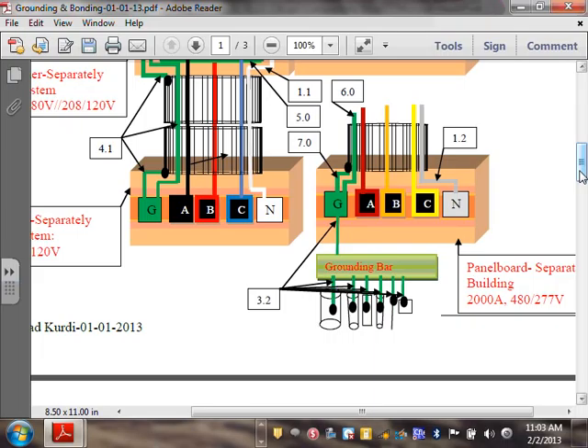I have 5 conductors. You have to pull the 3 phases, the neutral, right? Your neutral has to be sized, and you also have to pull an equipment ground conductor. Now the equipment ground conductor is the same way, except you're going to size it now for 2,000 amp. That's why I call it number 6. No changes. It's just another subpanel. Number 7, guys, is also the equipment bonding jumper, load side, same size. Same size, meaning the same process, except it's going to be sized for 2,000 amp. And what's the size, guys, that we came up with for 2,000 amp? 250. How much? 250. So this will be a 250. This will be a 250.